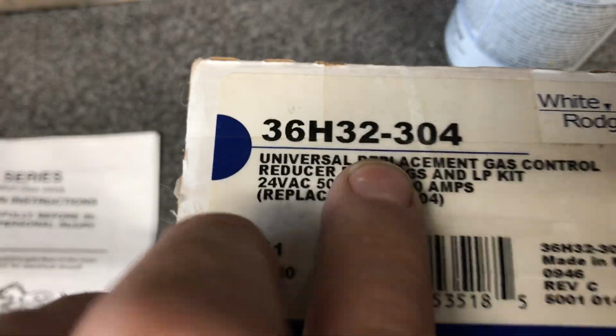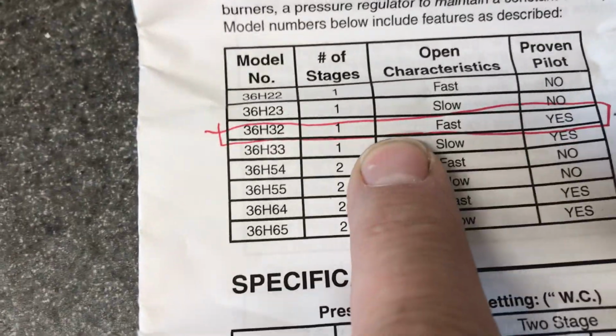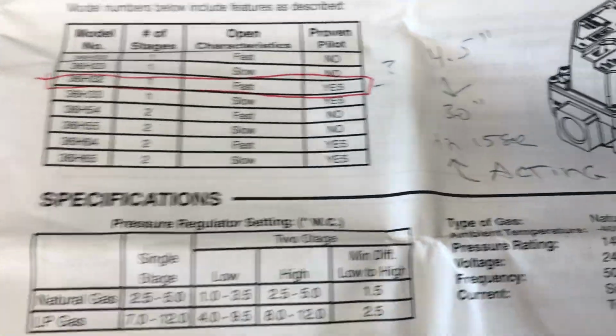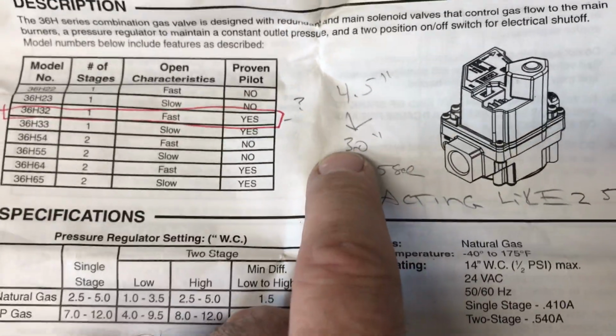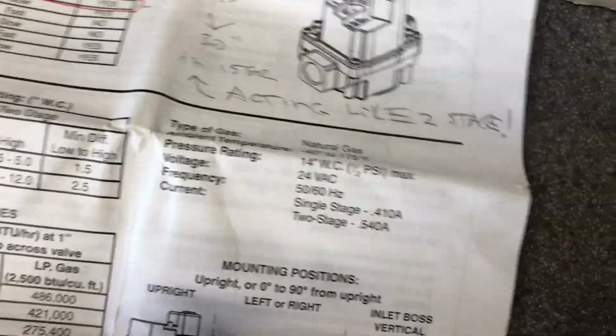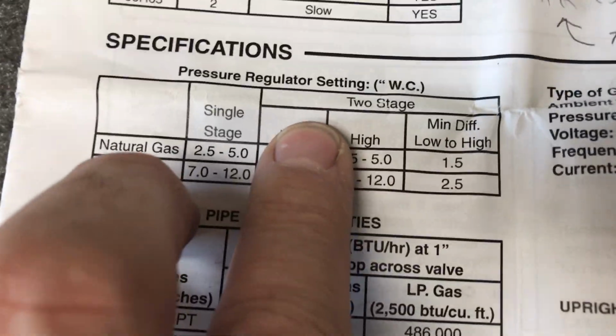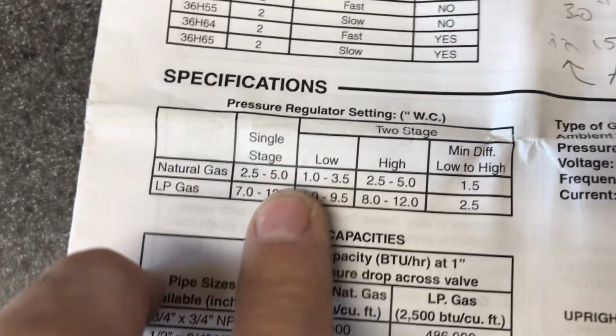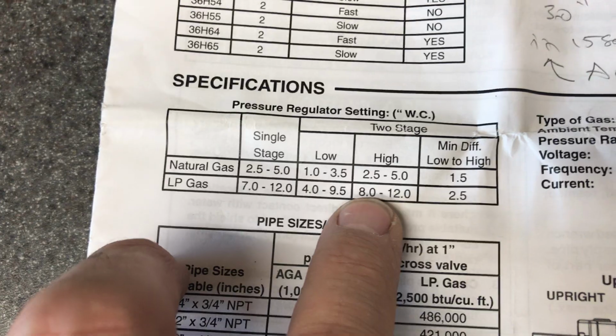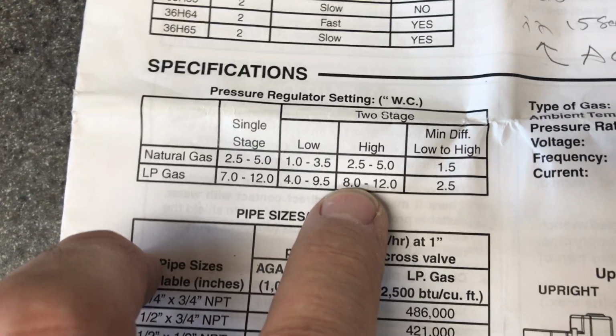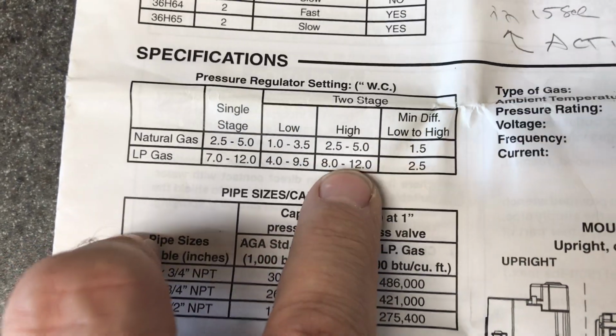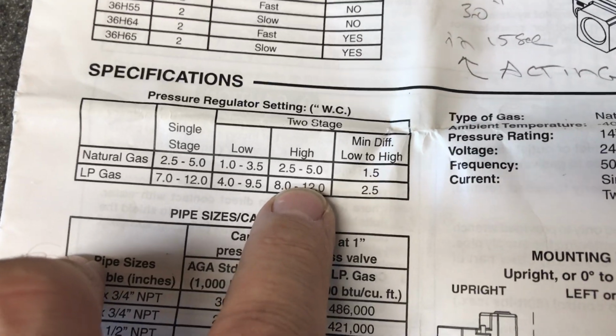It says here 36H32. 36H32, number of stages 1. Fast, yes. But mine is acting like a 2-stage with 4 1/2 inches of water column to start with, and it goes to 3. Which is weird, because here's the specifications if it were a 2-stage. For natural gas, single stage low is 1 to 3. And I had 3 inches actually. And a high is 4, right? 4 1/2, I think it was.